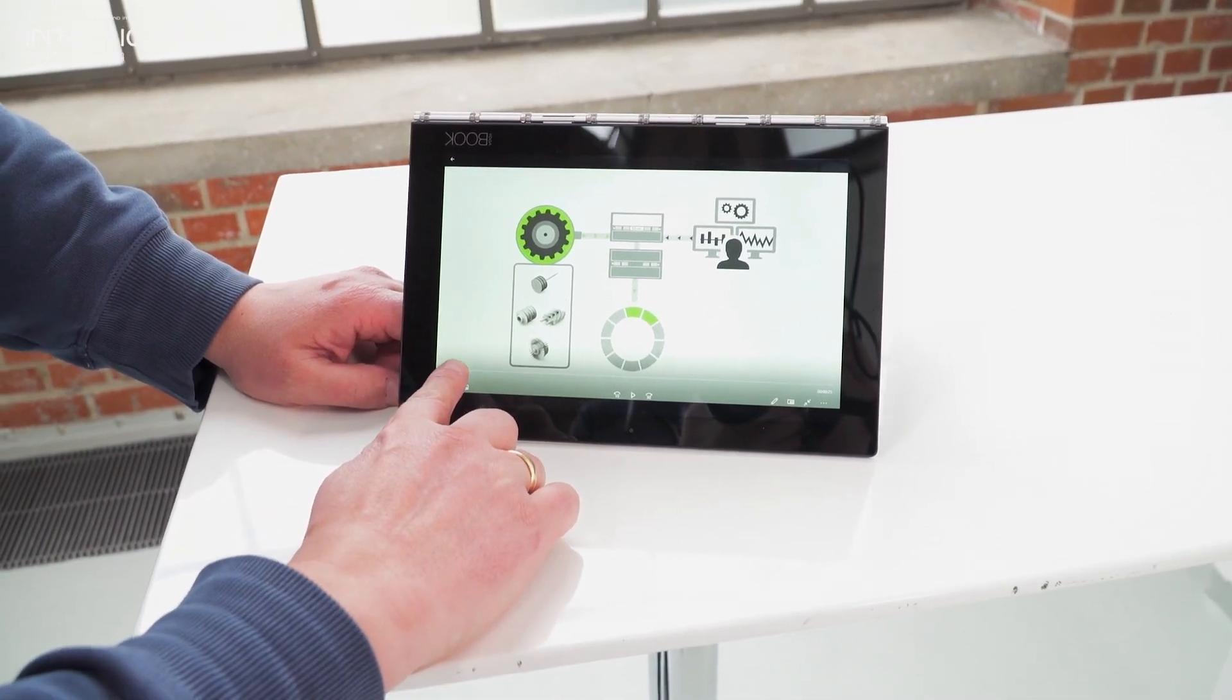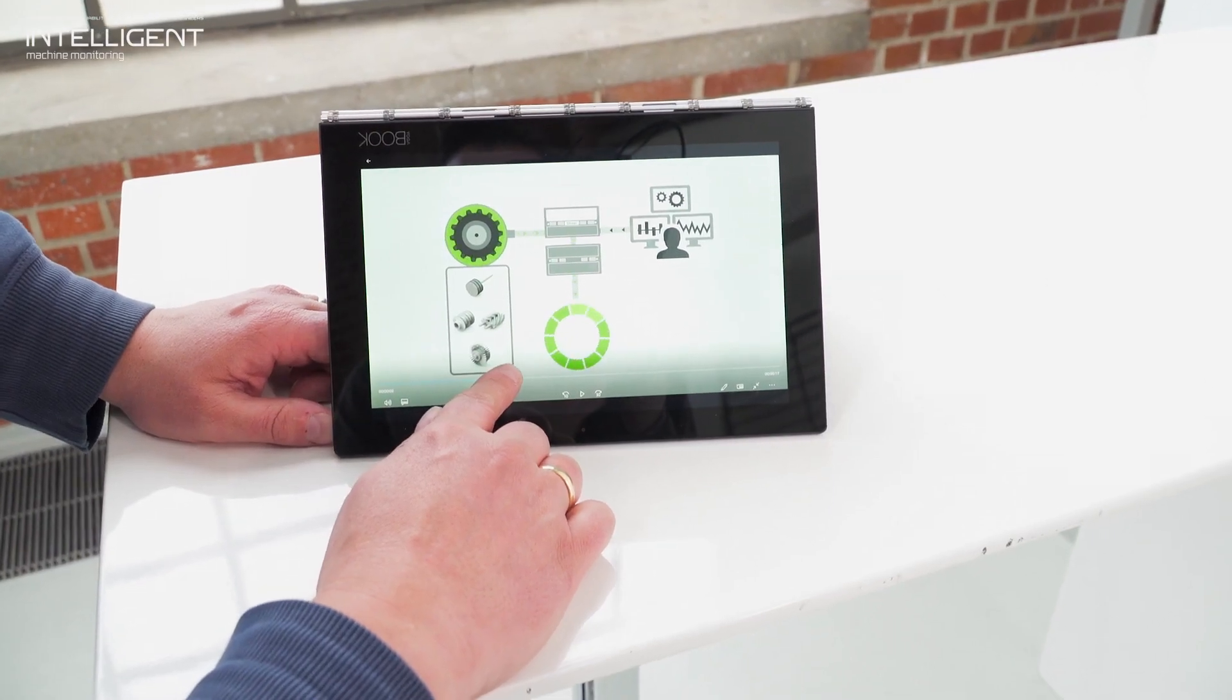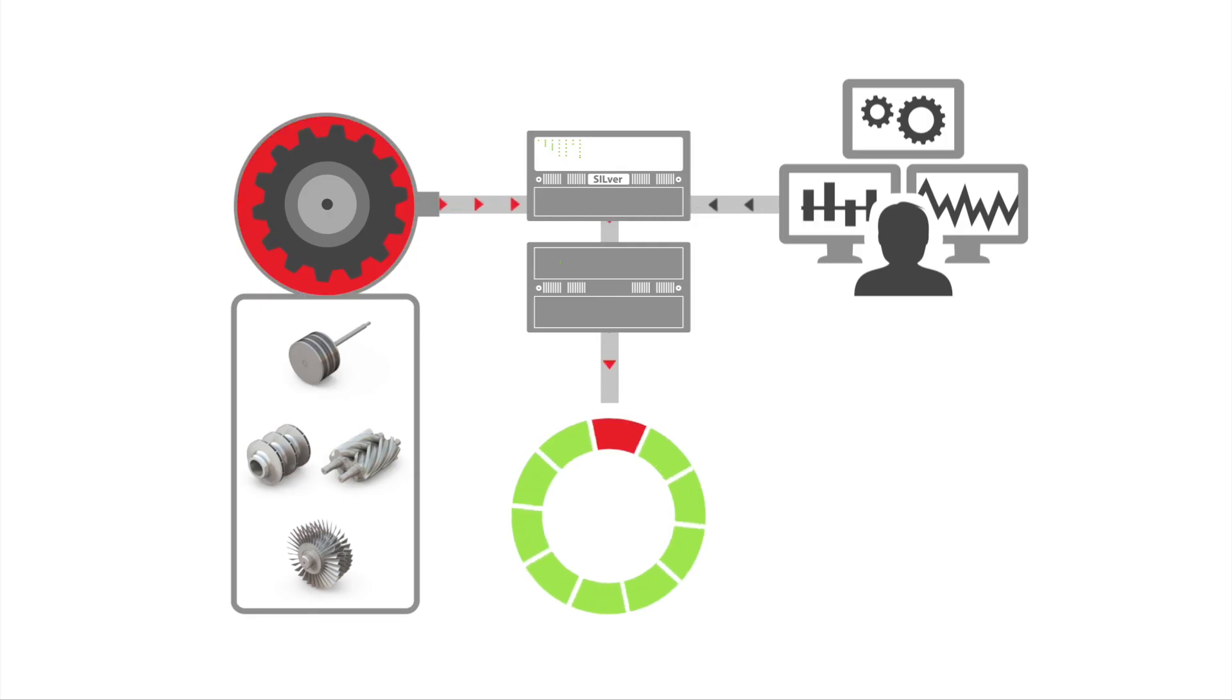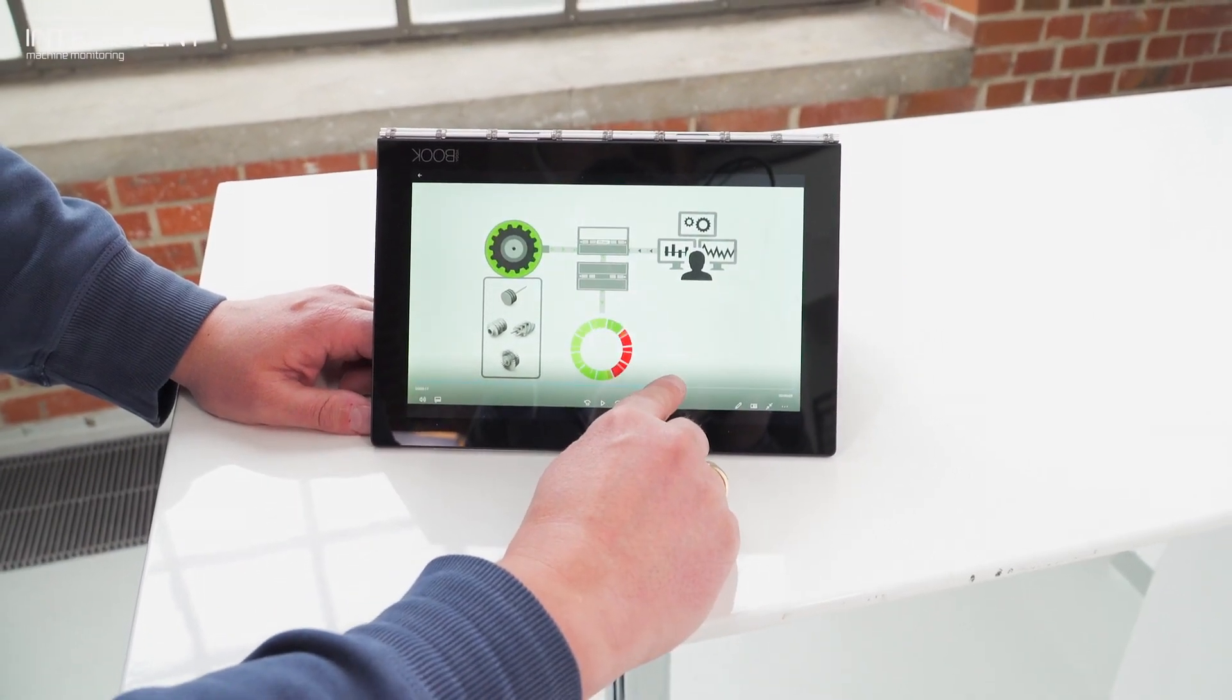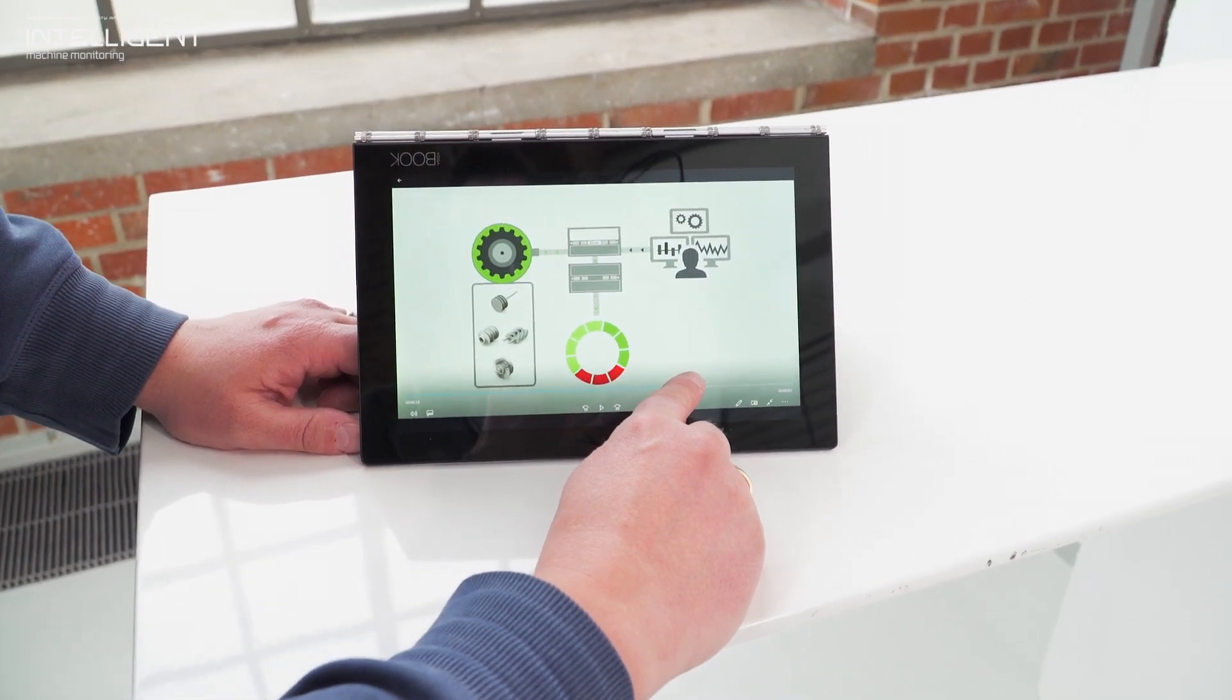So normally the ring buffer information will constantly record all information first in first out and overwrite it. But if an event occurred like here, the information will be recorded three minutes when the event occurred and seven minutes before.